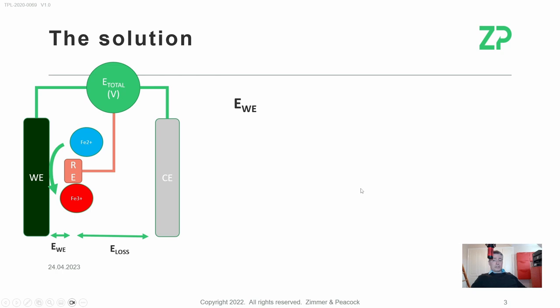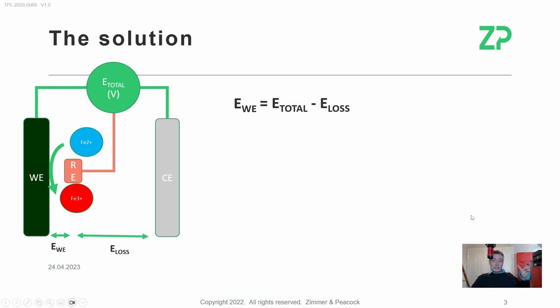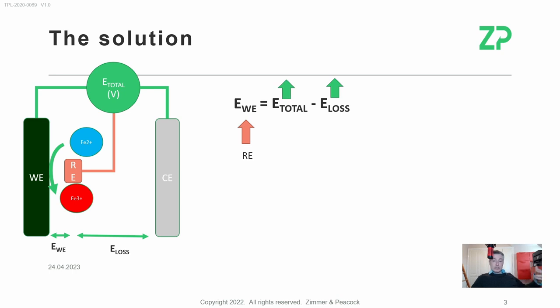What this meant was that they wanted to control the potential at the working electrode. It's straightforward enough to control the potential you apply across the working and counter electrodes, but as listed, it's very hard to control some of those losses. However, if you can measure the potential through the reference electrode, and if the losses have changed, you can adjust the applied potential accordingly.